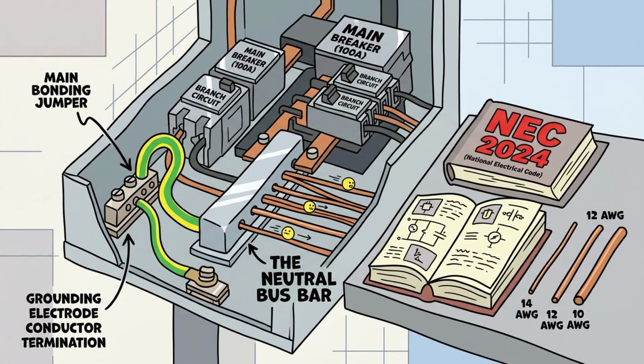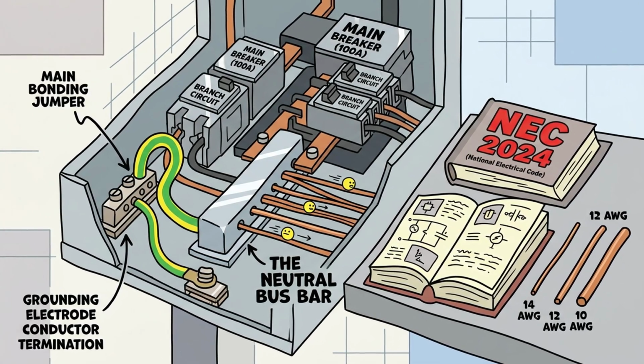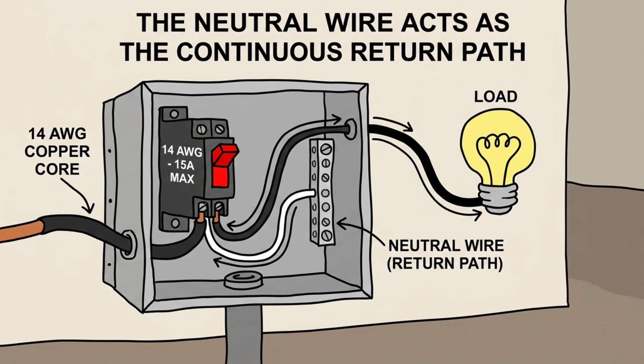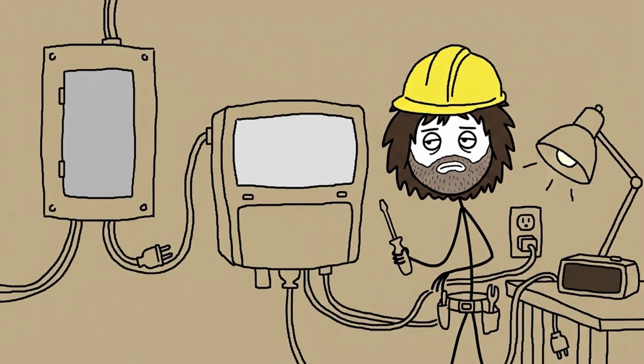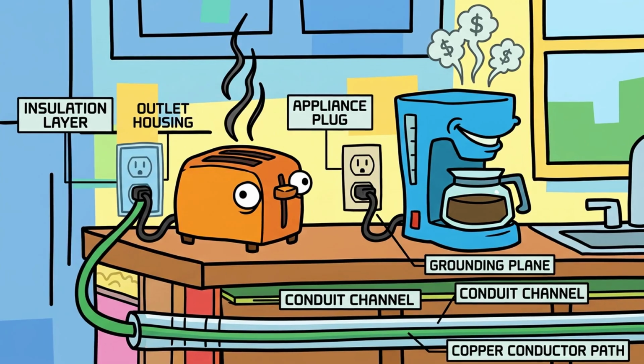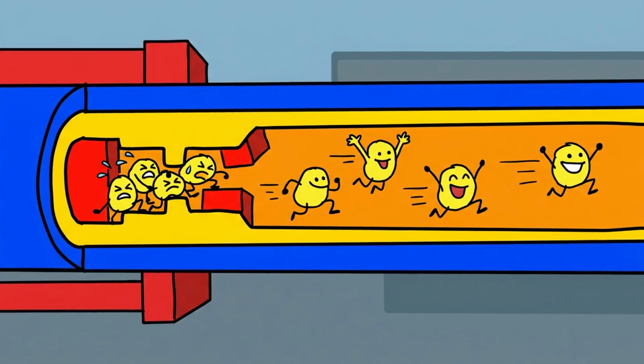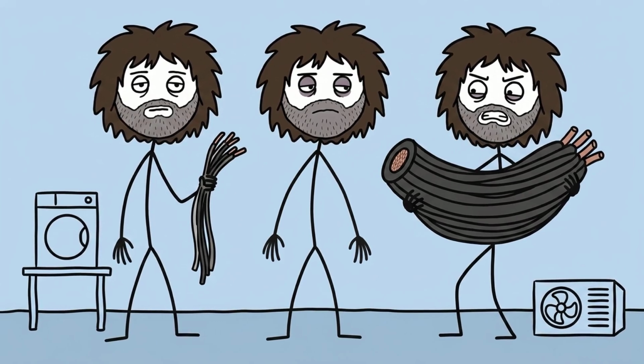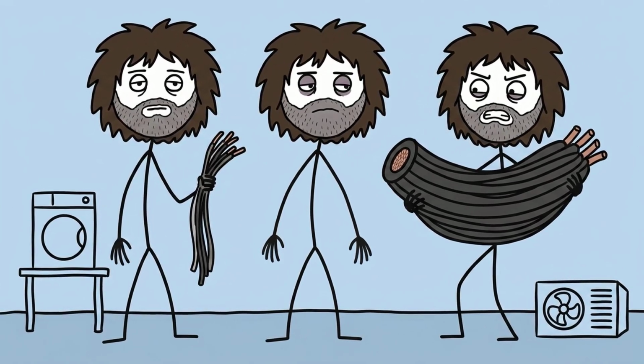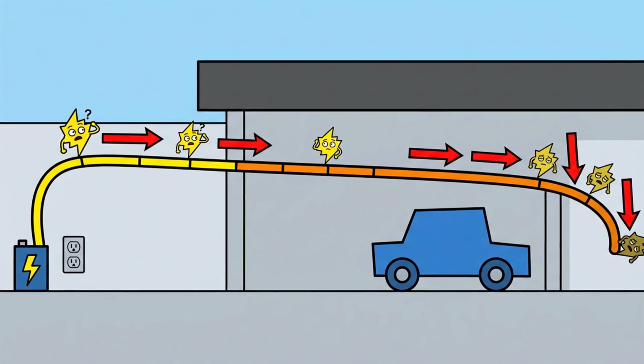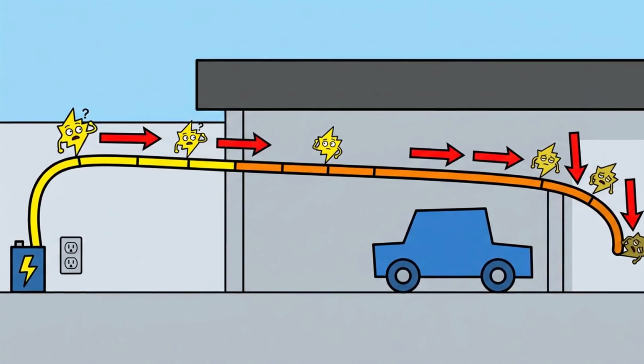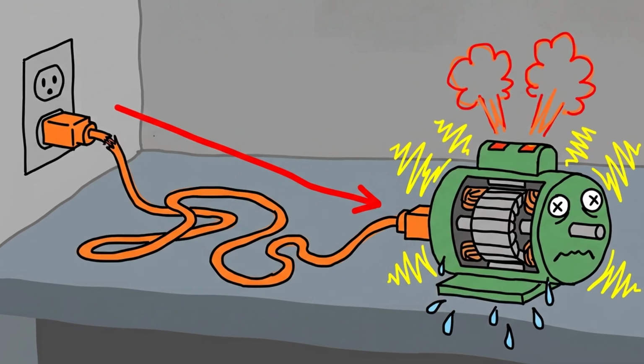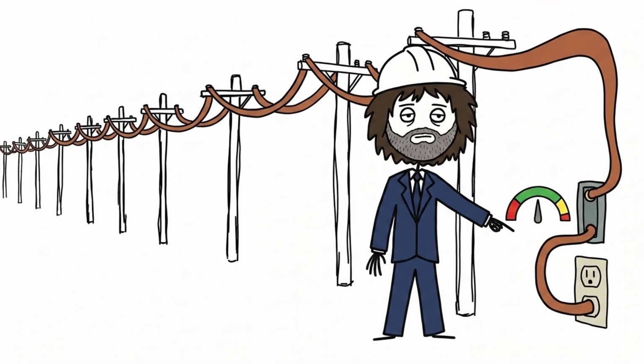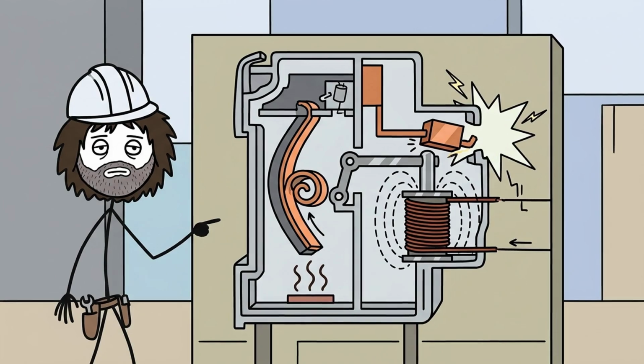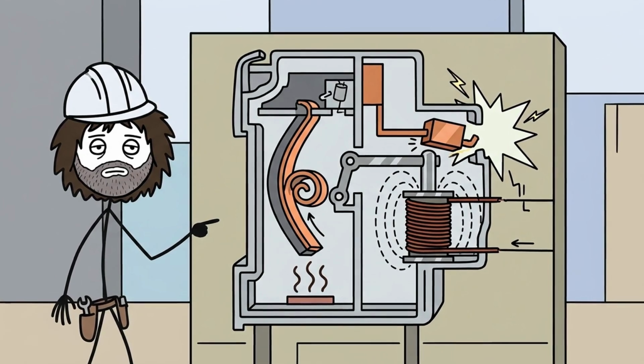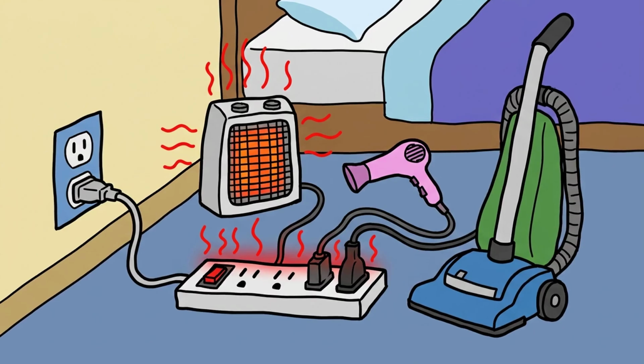At the heart of this gateway sits the neutral bus bar and main bonding jumper. The neutral wire acts as the continuous return path, completing the circuit back to the transformer. In your main service panel, and only in your main panel, the neutral bus bar is physically bonded to the solid copper ground rod buried deep in the earth. This bonding point establishes 0 volts potential relative to ground. If a hot wire touches a metal appliance casing, the ground wire provides a low resistance path back to the panel. This triggers an immediate flood of current that trips the breaker instantly, preventing electrocution.